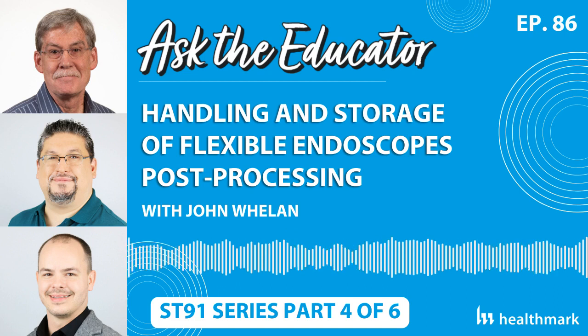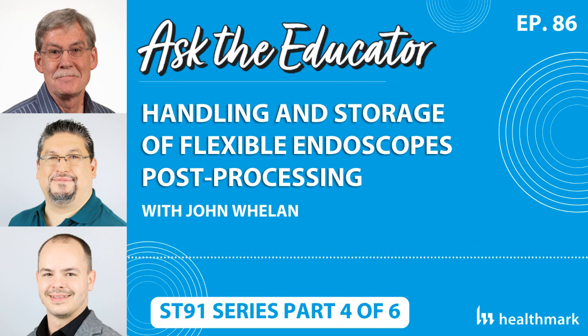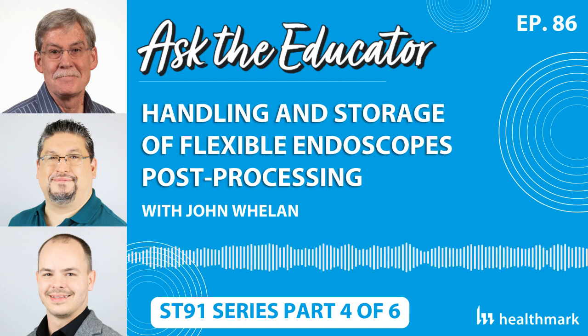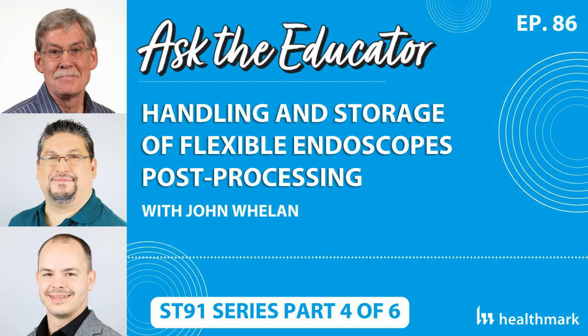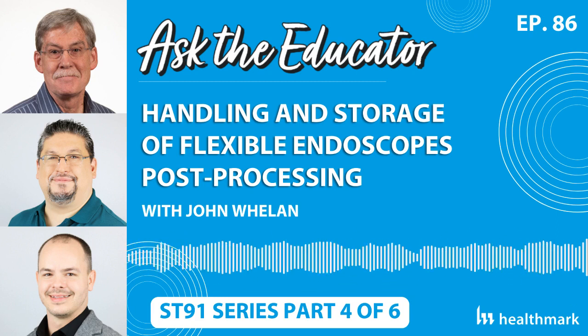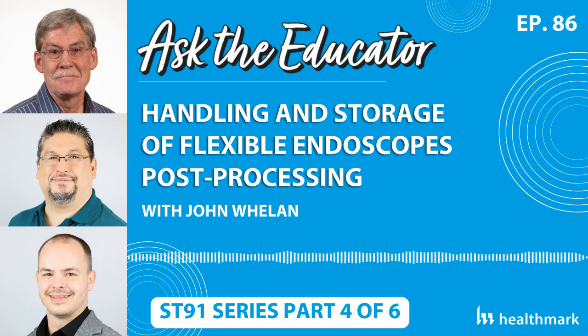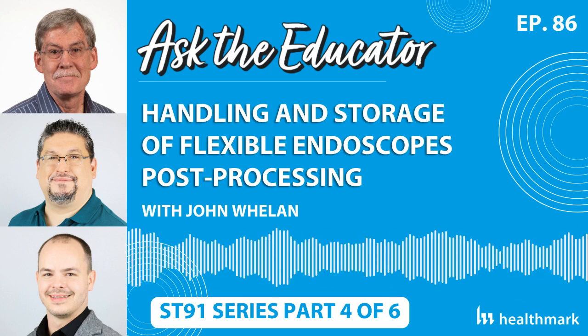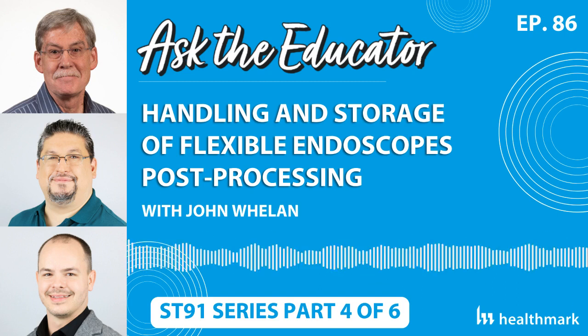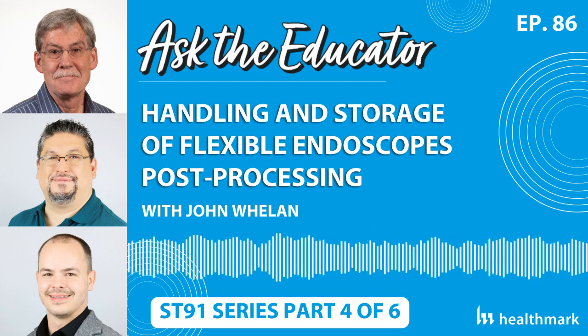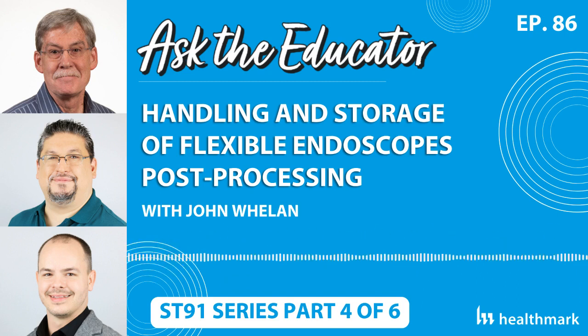Adam, do you feel like that touched on what you were hoping? Correct. And that's the idea that when the standard says something is preferred, it's sort of like, well, look, if you're in the market for a new cabinet anyway, here's what the standard says is preferred. Try to go for this if you can, because this has shown better results than the alternatives. So that's all that standard is saying. But if you have an existing cabinet that's compliant and it has HEPA filtered air, it does all the things minimally that we want, then you're fine with that because that's the minimum standard.